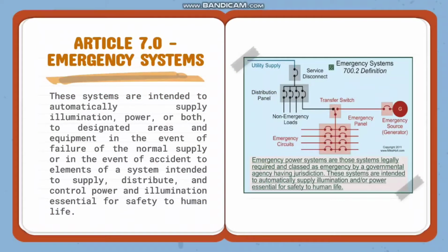Article 7.0 Emergency Systems. These systems are intended to automatically supply illumination, power, or both to designated areas and equipment in the event of failure of the normal supply or in the event of accident to elements of a system intended to supply, distribute, and control power and illumination essential for safety to human life. So, if the backup power systems are legally required and essential for safety to human life, these systems are classified as emergency systems.